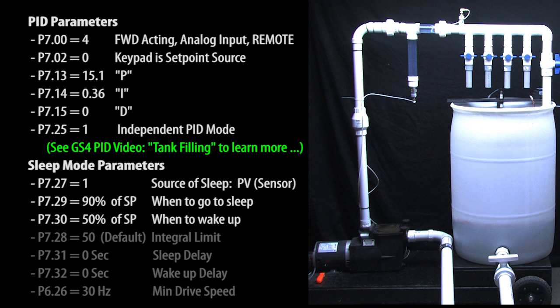There's just one more thing to do. When the drive turns the motor off and the water level falls, the PID algorithm hasn't gone away. It's still trying to get the water level to the set point. Of course it can't because sleep mode turned the motor off.